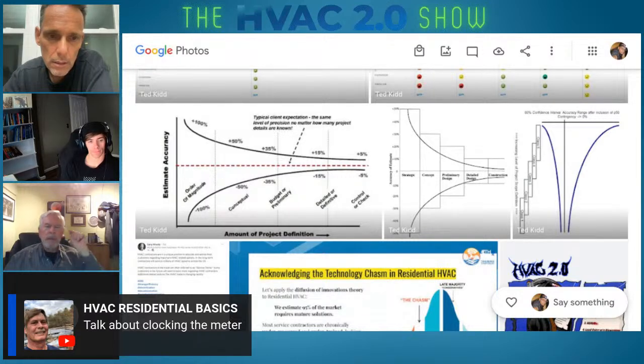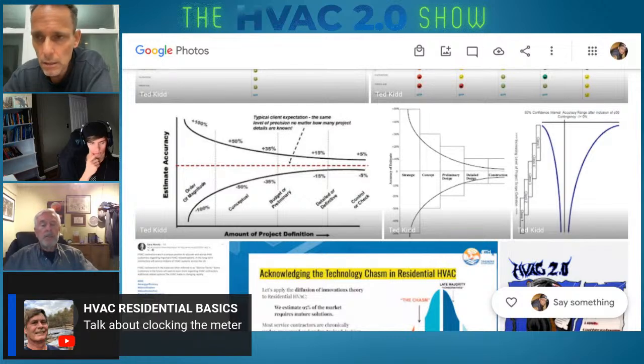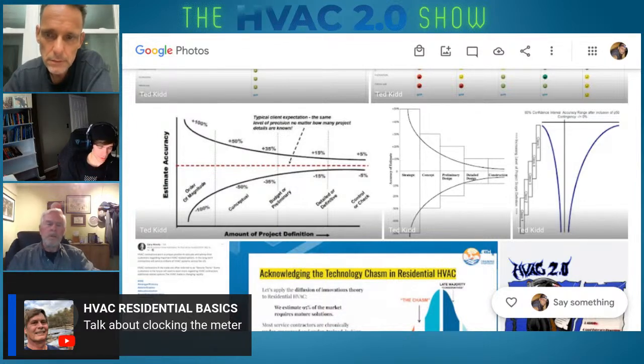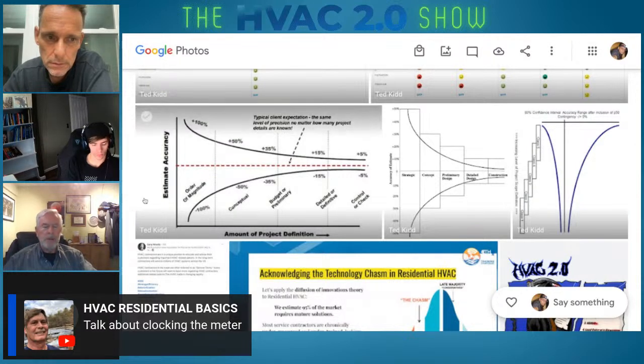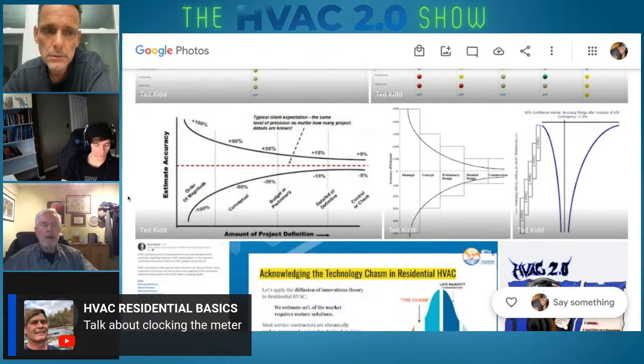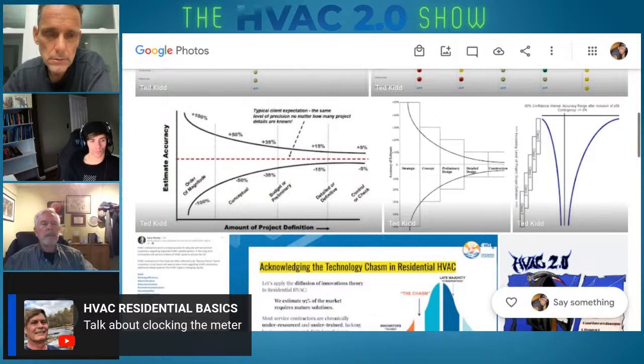But you'll get a better idea of what your energy use is by looking at your gas bills. Disaggregate the gas bills so you know how much fuel you've used. Clocking the gas meter is helpful for accurately setting up the furnace, to make sure that it's not overfiring and stressing the heat exchanger because of that.